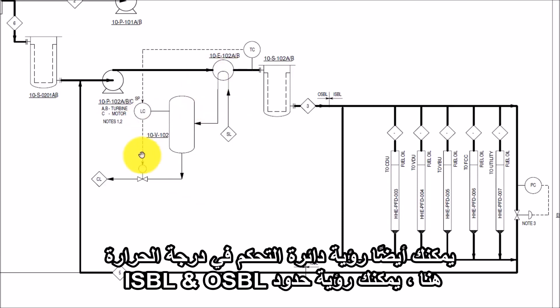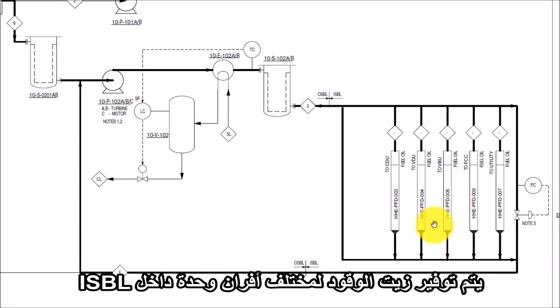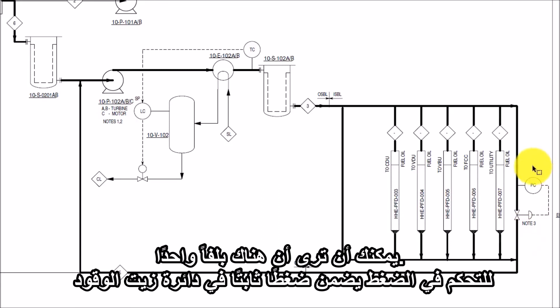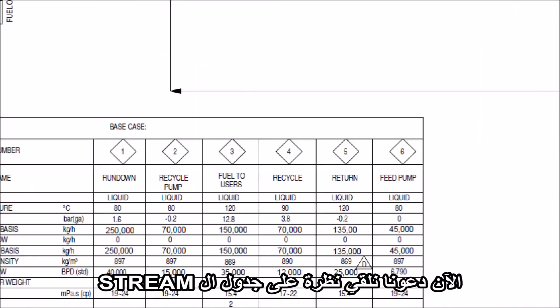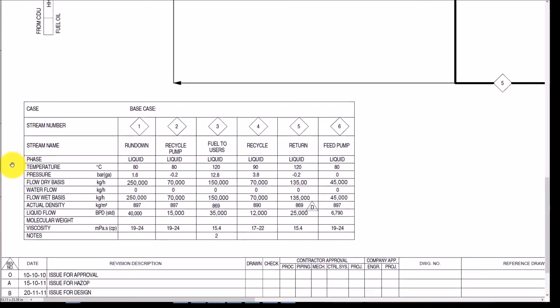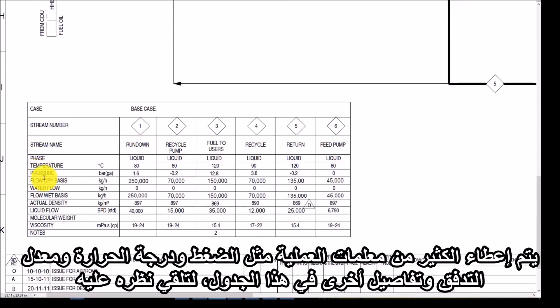You can see the temperature control loop as well. Here you can see the battery limit of ISBL and OSBL. Fuel oil is supplied to various ISBL unit furnaces. On the ISBL side, you can see that one pressure control valve is given, which ensures constant pressure in the fuel oil loop. Now let's look at the stream table. Lots of process parameters such as pressure, temperature, flow rate, and other details are given in this table.